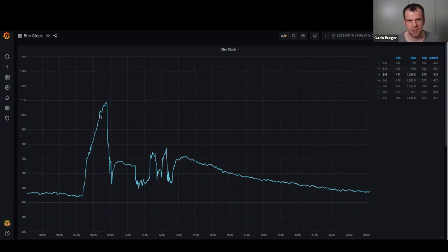But now think this room is equipped with a CO2 traffic light alarm system. So the teacher gets an alarm signal, a yellow, when we're over 1,000. If you don't have this system in place, imagine what happens with this curve just traveling up and up and up. In Germany, the classes are like 45 minutes, and then there's a break of 5 or 10 minutes. You could easily hit 2,000 and 3,000 ppm.